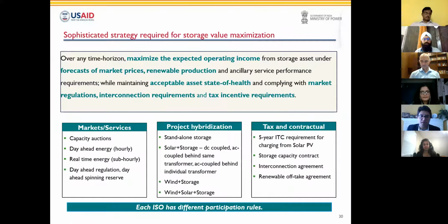That's point 1, equitable market services. Point 2 is sophisticated controls and dispatch strategy. In order for the battery system to bundle and respond to all these different markets, the internal control system has to perform dispatch optimization. The requirement is to maximize the expected operating income of the storage asset under forecasts of market prices and renewable production, ancillary service performance requirements, while maintaining acceptable state of health and complying with market regulations, interconnection requirements, and incentive requirements.